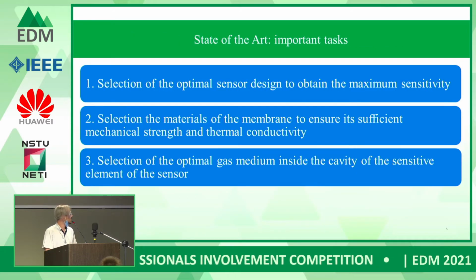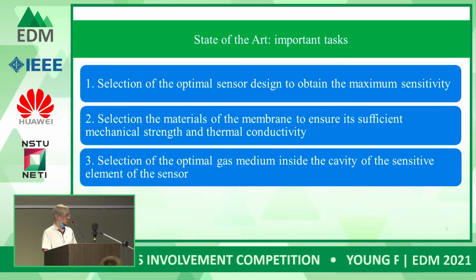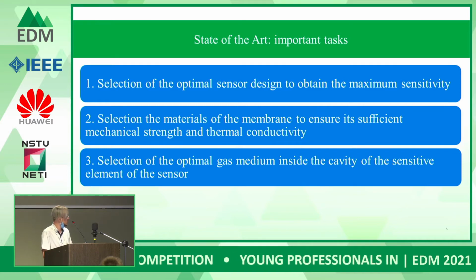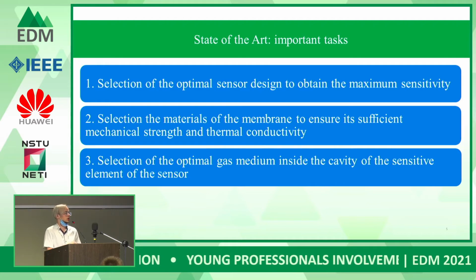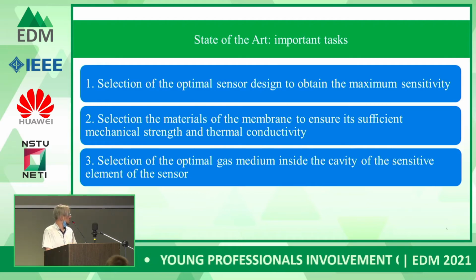The main tasks are selection of the optimal sensor design to obtain maximum sensitivity, selection of the membrane material to ensure sufficient mechanical strength and thermal conductivity, and the last, selection of the optimal gas medium inside the cavity of the sensitive element of the pressure sensor.